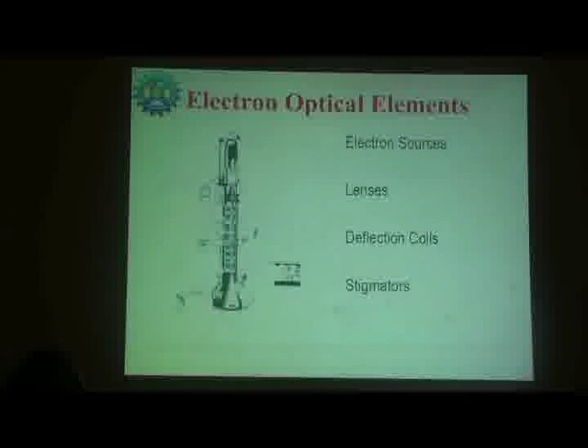So the electron optical column, what we have decided, has these parts. Electron sources are the primary factor. That is how one decides on the microscope: they will ask whether it is tungsten based, LaB6 or field emission. So the electron source is the first deciding factor of the microscope. Then come all these lenses, deflection coils and stigmators, which are part of the microscope. So we have different sources.